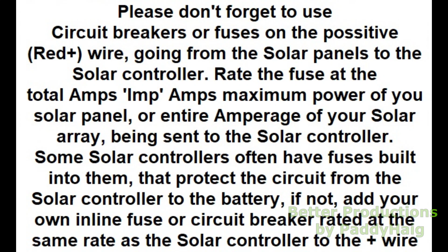This fuse, more often than not, relates to the leisure battery side of the solar controller circuitry, so you should always put a fuse or circuit breaker on the solar panel side of the circuit between the solar panel and the solar controller. I like to use a circuit breaker rated at the maximum Imp of my solar panel, or the calculated combined maximum amperage rate of my solar panel array, taking into account the wiring method used. Please see my tutorial number 9 on solar panel basics.